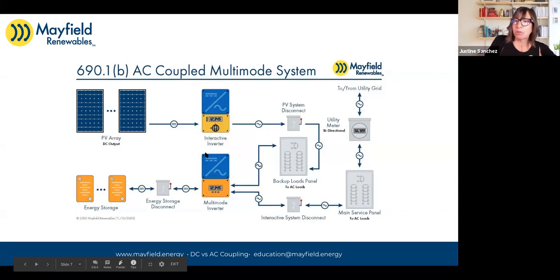A DC coupled system could be more efficient in the sense that we only have one inverter in a DC coupled system rather than two like we have here in the AC coupled system. So if we are having to run our PV array through our interactive inverter, there's an efficiency loss there. And then let's say we're utilizing that PV power to charge batteries. We have to change it from AC back to DC to get into the batteries, and then out of the batteries, from DC back to AC to our backed up loads panel, say at night. Okay, and then you have efficiency losses here and here with an AC coupled system if you're utilizing that power at night.